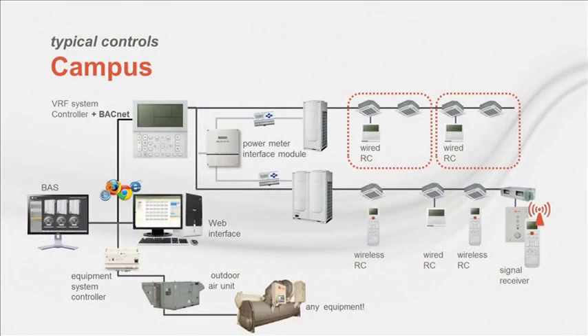Finally, using a system controller that uses BACnet communication protocol allows a designer to interconnect the VRF system into any compatible enterprise control system, allowing integration with other systems throughout a building or campus. When we put all these components together, we end up with a complete VRF system. Earlier, Eric discussed the difference between a heat pump and heat recovery VRF system. In a heat pump system, the outdoor unit can only be in heating or in cooling mode. It cannot satisfy indoor spaces that have conflicting comfort needs.